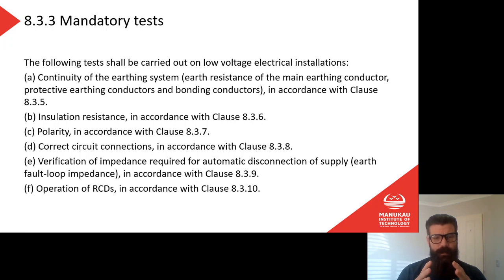So I need to test the continuity of every earth wire inside an installation. And there's a table in section 8. If you want to go and have a hunt around and find that, it might be table 8.1 or 8.2. I can't remember off the top of my head. But that tells us what the resistance values should be for the earthing system, depending on the situation, size of the cables, all of that kind of stuff. Again, we get into much more detail on earth testing later on, but that's it in basic terms.